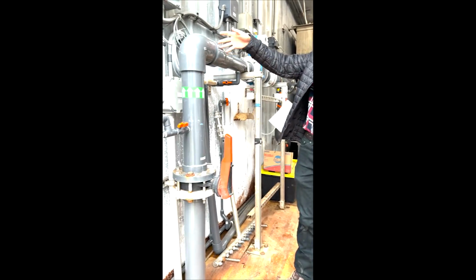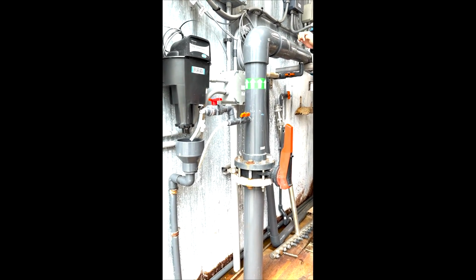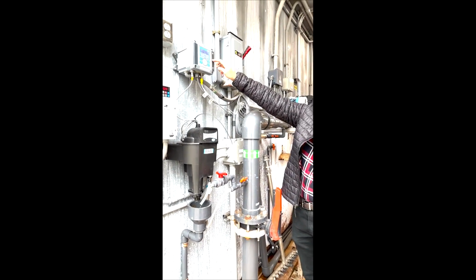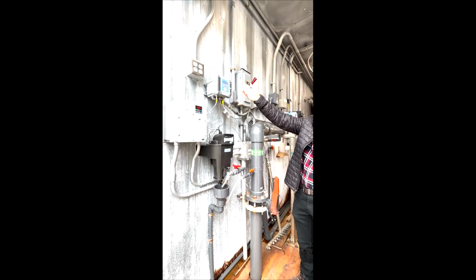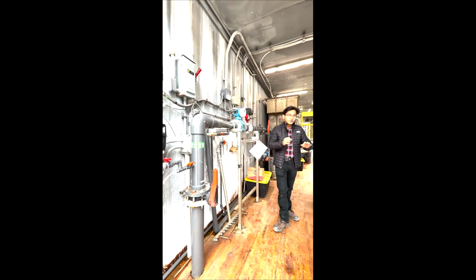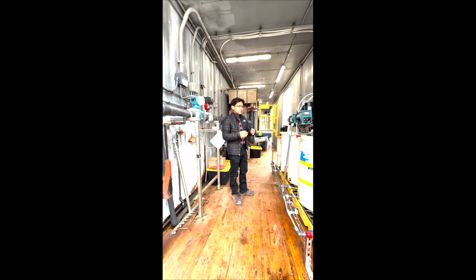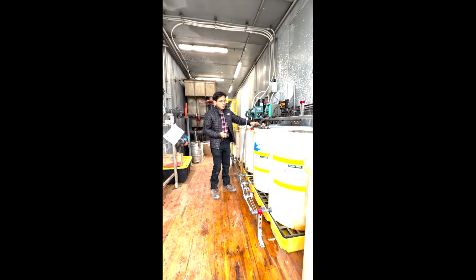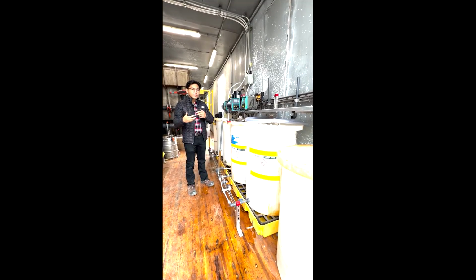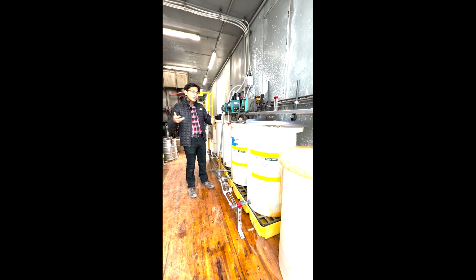Water comes in through here, and as you can see, we have measurement equipment to assess the quality of it: the temperature, how cloudy the water is, and also its pH. As the water comes in, we have two chemicals that we're using to treat the water. The first is called a coagulant. This allows us to destabilize the contaminants and make sure that they can come out of the water.